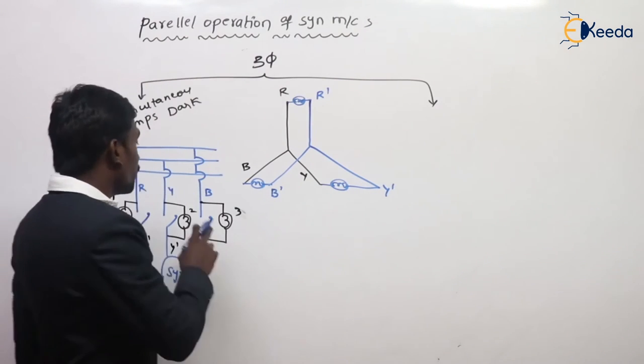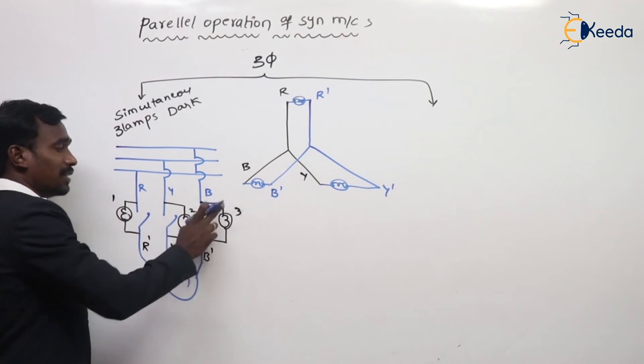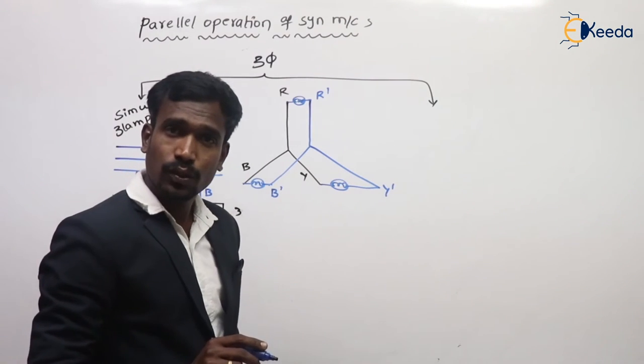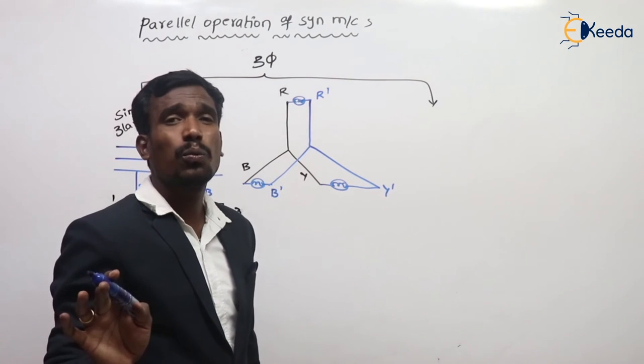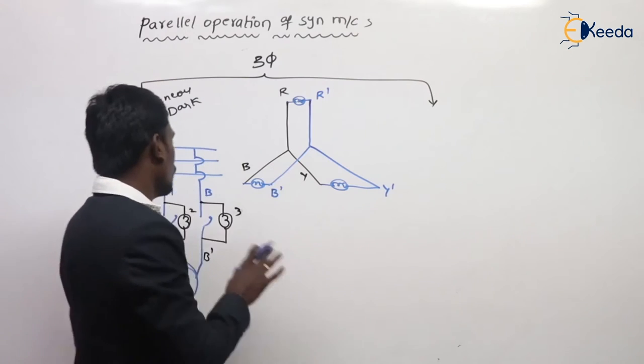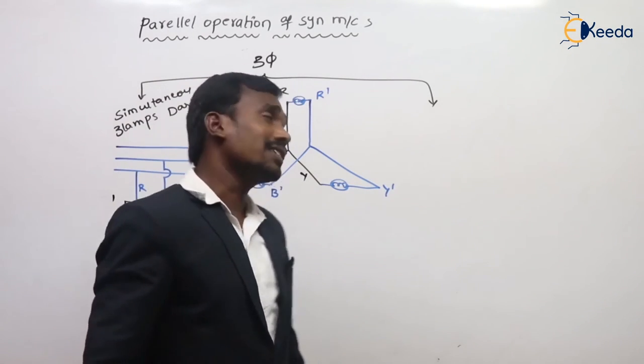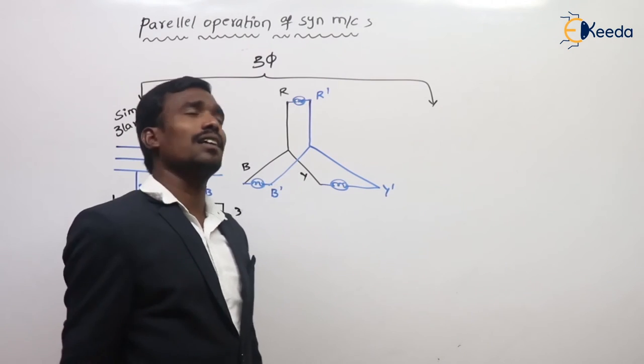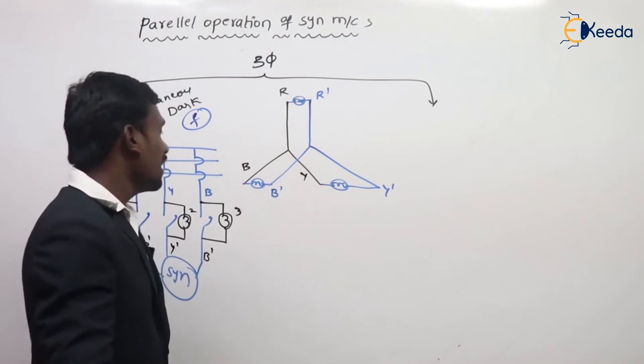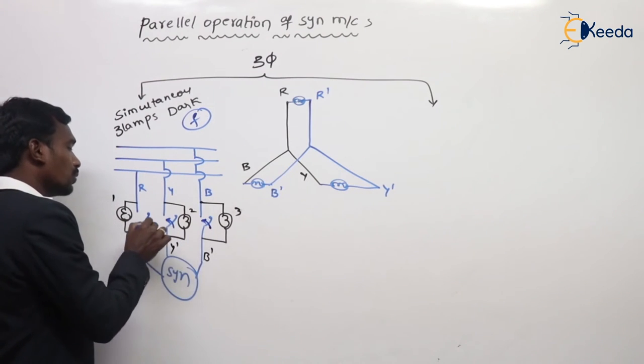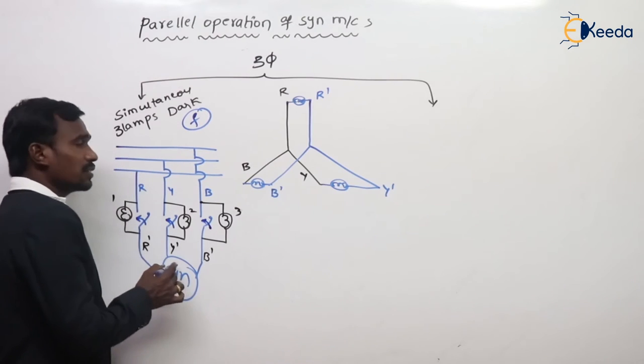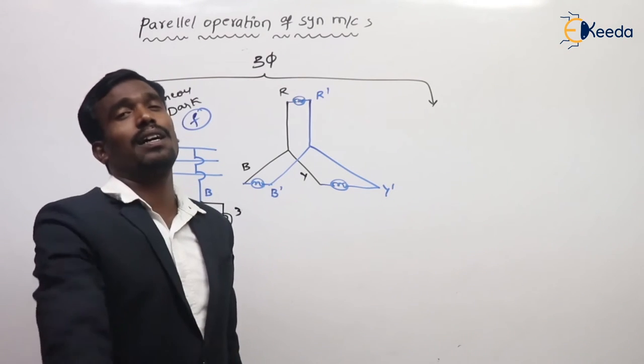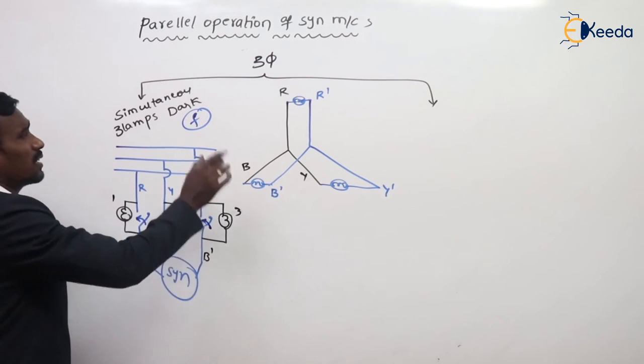The phase sequence is also important here — R with R', Y with Y', B with B'. We must maintain same phase sequence; then only the lamp method will work. Phase sequence should be same first, and second, frequency should be same. When the three lamps give simultaneously dark, at that condition we close the switch and the machine synchronizes with the bus bar. This is the three lamps dark method.